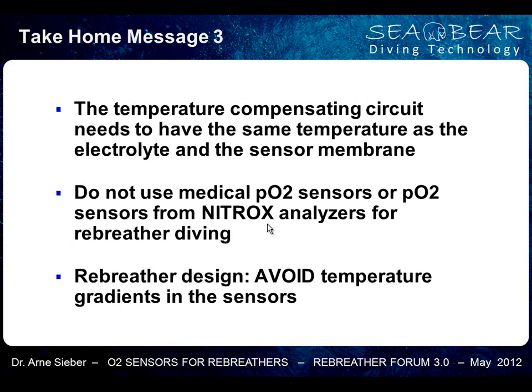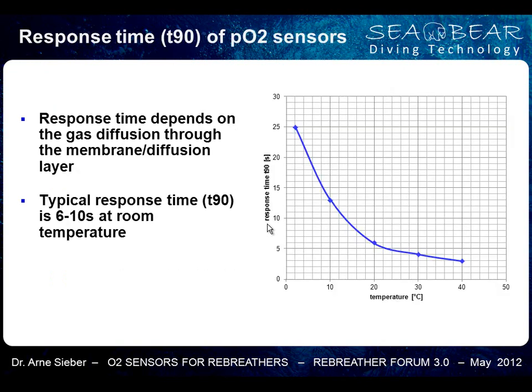The next thing is rebreather design: avoid temperature gradients inside the sensor. If you have one part of the sensor that is cold and the other side warm, you have some kind of gradient, and you don't know if the sensing element on the back has the same temperature as the sensor cell. So you will get some wrong readings.